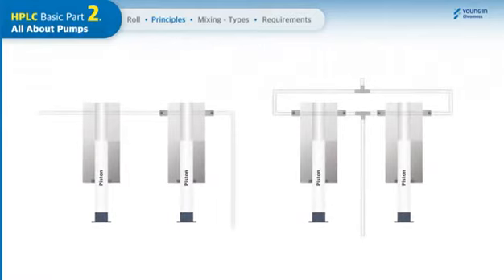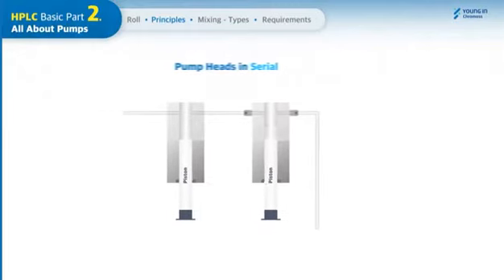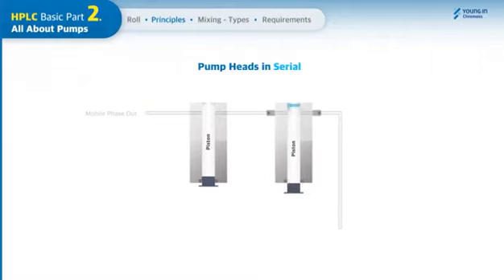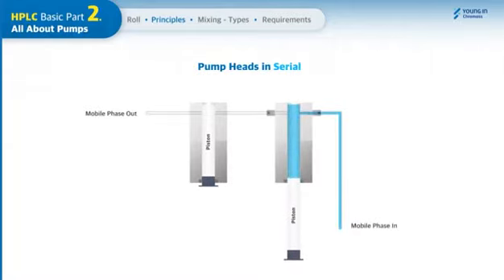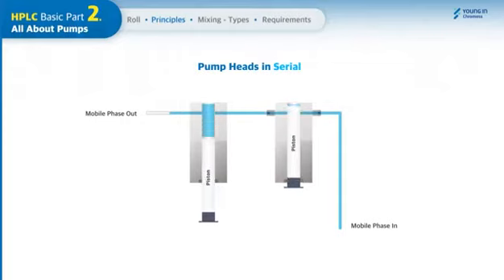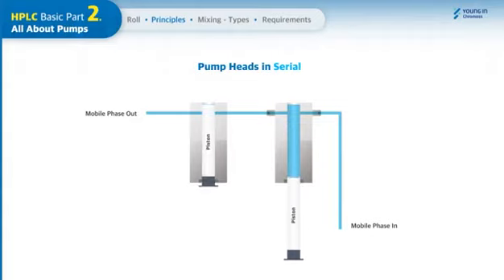HPLC pumps can be classified into two major types, which are serial and parallel, depending on their mechanism. Let's see how the pump head in serial works. When a piston of the primary pump head is pulled out to draw the mobile phase, the pump head is filled with the mobile phase. And when the primary piston pushes the mobile phase, the half of mobile phase flows out to the system and the rest will be filled in the secondary pump. The secondary piston pushes the rest of the mobile phase into the system, while the primary piston is pulling out the mobile phase to fill the primary pump head.